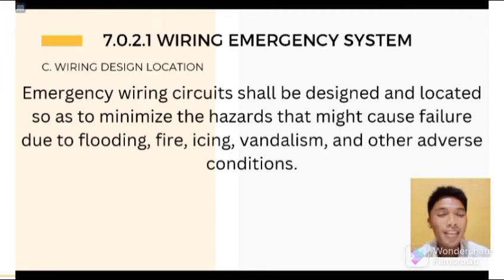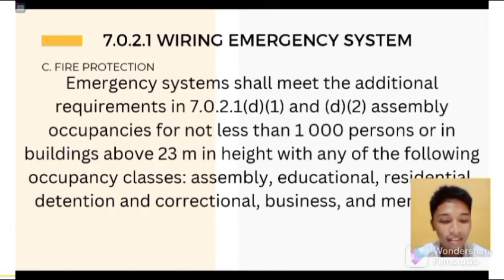Letter C, wiring design and location. Emergency wiring circuits shall be designed and located so as to minimize the hazards that might cause the failure due to flooding, fire, icing, vandalism, and other adverse conditions. Letter D, fire protection. Emergency systems shall meet the additional requirements in 7.0.2.1 letter D number 1 and letter D number 2, assembly occupancies for not less than 1,000 persons or in buildings above 23 meters in height with any of the following classes: assembly, educational, residential, detention and correctional, and business mercantile.